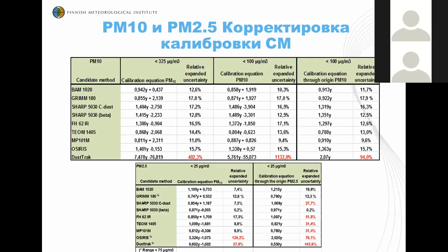This slide is an example of the results for the equivalence test. The equivalence test basically gives two kinds of information to be utilized for your measurements with the specific instruments. First, it answers whether the non-reference method is equivalent or not. If it's not equivalent, it cannot be used for the official measurements in the country. That's quite vital. And this is an example that in Finland we found that some of the equipment doesn't pass the equivalence test at all. These are the red ones here.